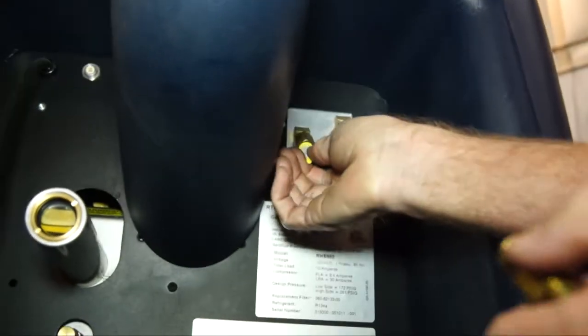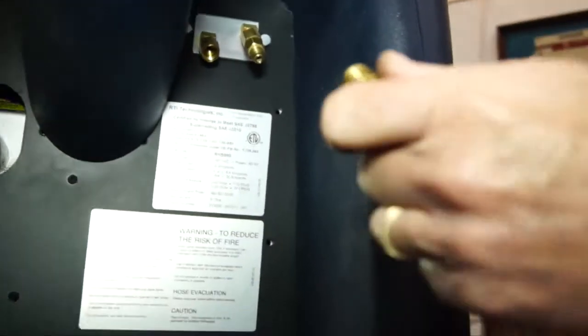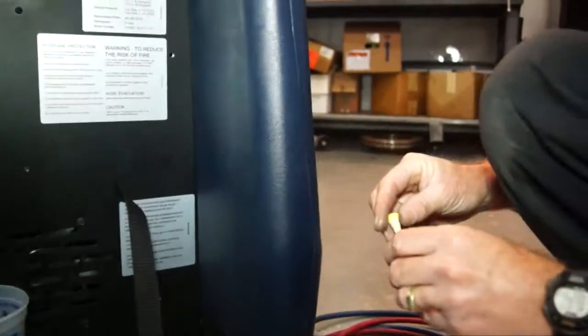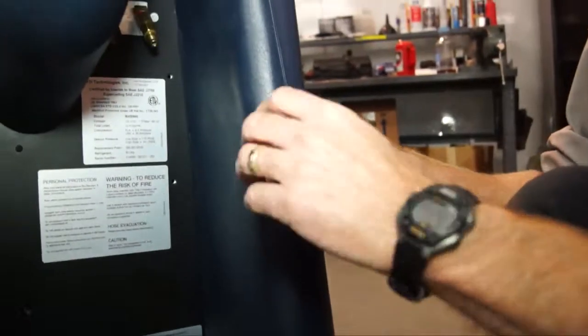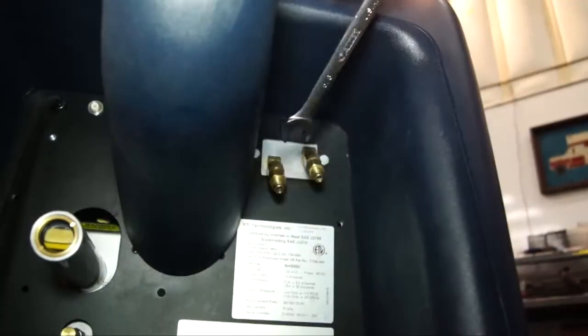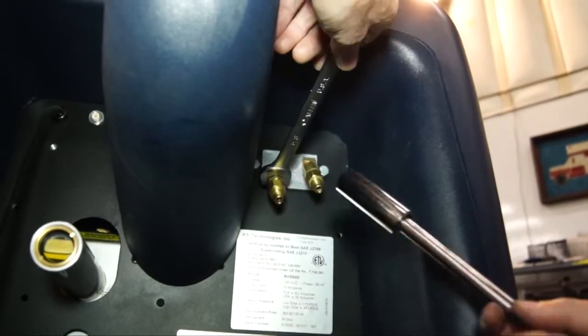And as you notice, the low side, again, it's very, very clean. But I have it out, so I'm going to replace it and put a new filter in that as well. And when you put these back in, you may want to put a little oil on that O-ring. And I'm going to tighten them back up. Again, use my backup wrench.